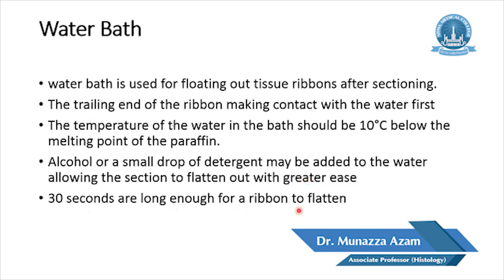Water bath is used for floating out tissue ribbons after sectioning, with the trailing end of the ribbon making contact with the water first. The temperature of the water in the bath should be 10 degrees centigrade below the melting point of the paraffin. Alcohol or a small drop of detergent may be added to the water, allowing the section to flatten out with greater ease. 30 seconds are long enough for a ribbon to flatten, and then these sections are taken up on slides and then covered by a cover slip and fixed.